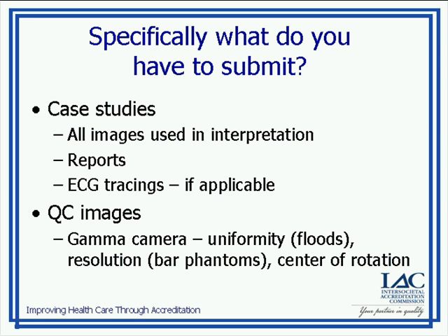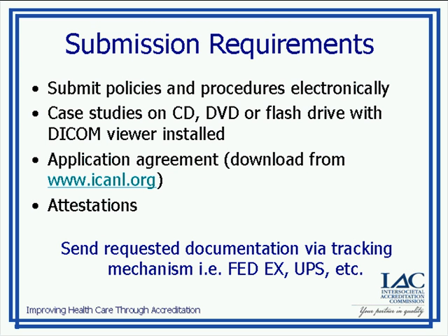So we want to see your uniformity, or your floods. We want to see your resolution linearity images, which is your bar phantoms, and we want to see your most recent center of rotation. When you submit your application, you're going to upload all of your policies and procedures electronically, but you're going to send your case studies to us, and we prefer that you send us electronic images on a CD, DVD, or flash drive. And we appreciate that some labs don't have the ability to actually submit electronic data.